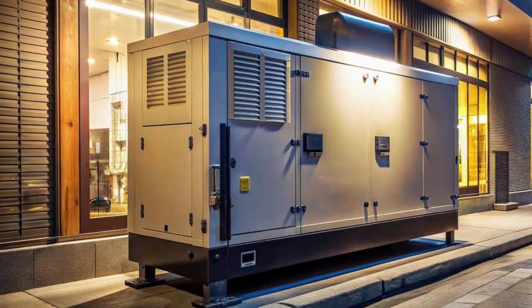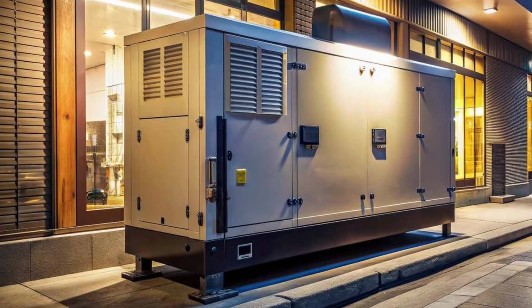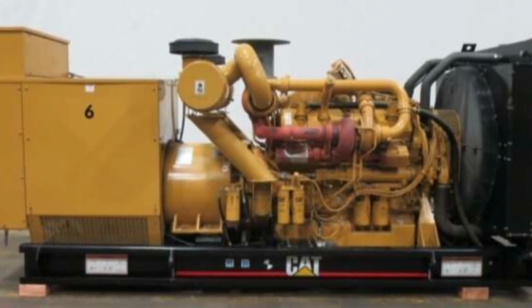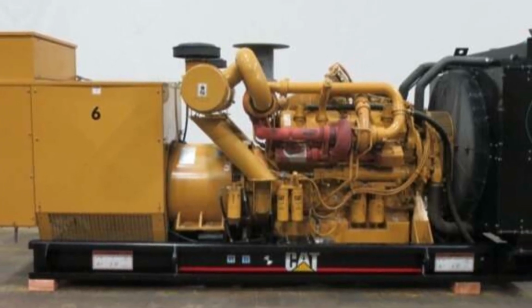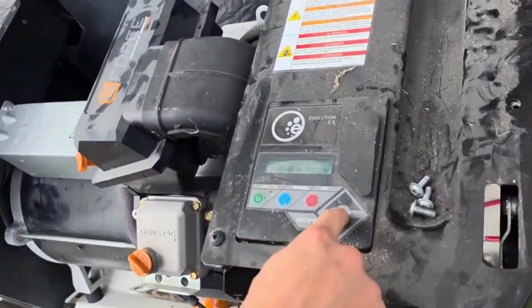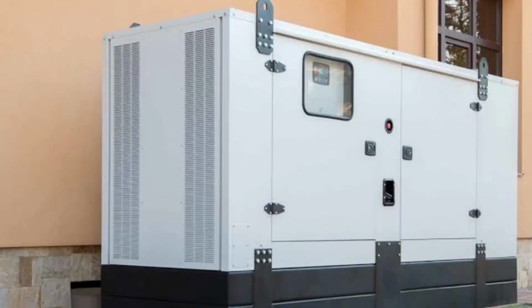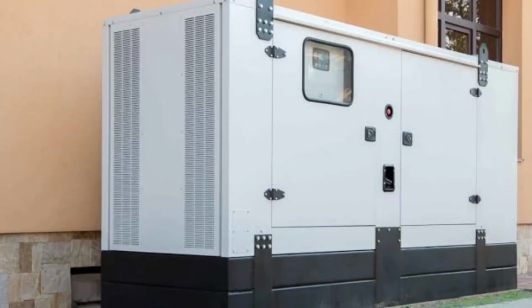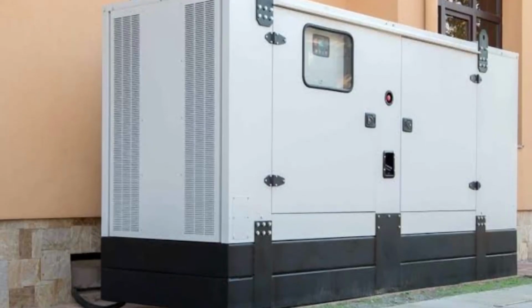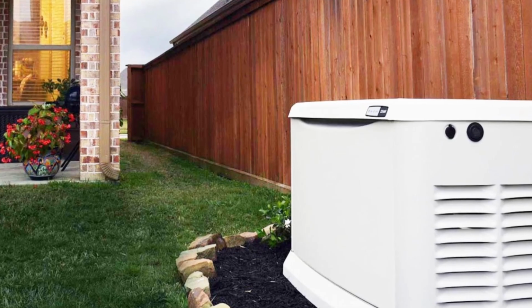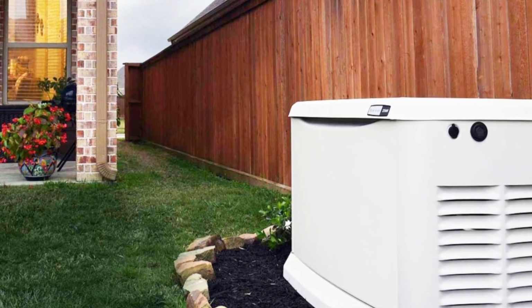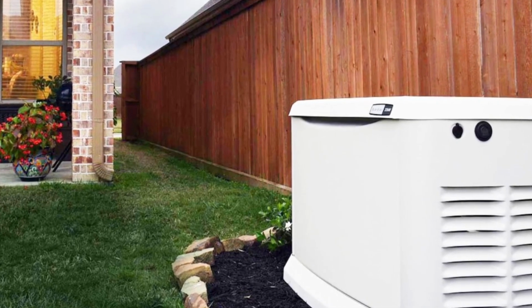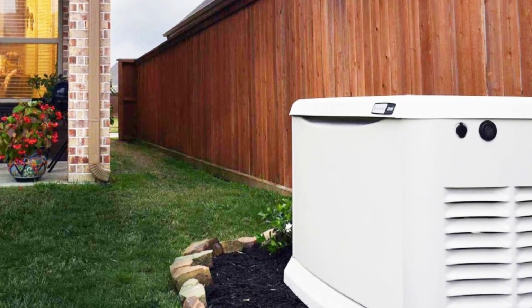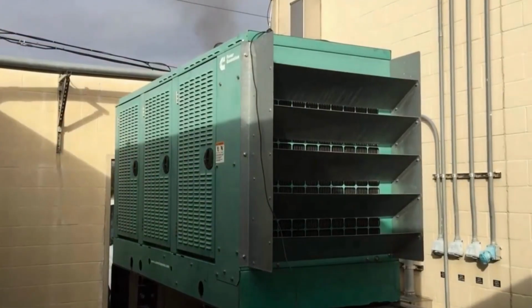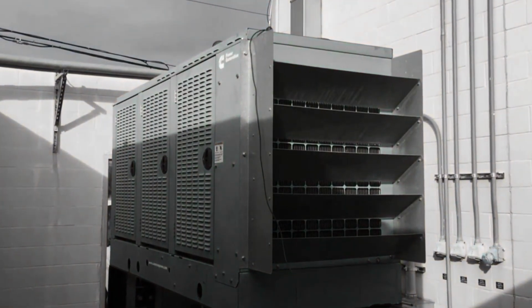Another phrase that deserves a closer look is whole home coverage. It sounds like a technical guarantee, but it's really a marketing term. Take the Cummins RS-20A, a 20 kW standby generator often advertised for homes up to 2,000 square feet. That recommendation is based on average power usage, not what happens when your furnace, well pump, refrigerator, and water heater all start at the same time during a real outage.